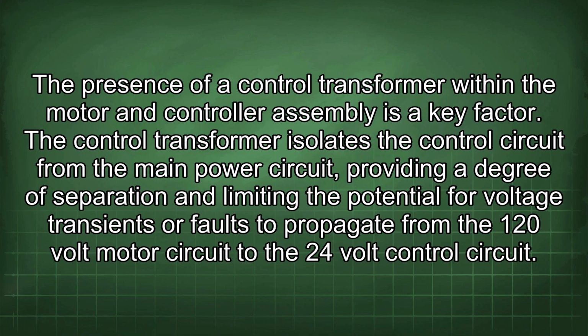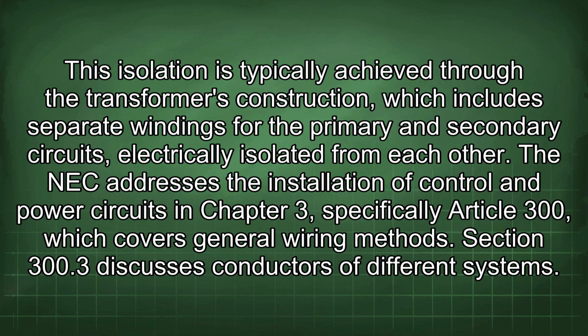The presence of a control transformer within the motor and controller assembly is a key factor. The control transformer isolates the control circuit from the main power circuit, providing a degree of separation and limiting the potential for voltage transients or faults to propagate from the 120-volt motor circuit to the 24-volt control circuit. This isolation is typically achieved through the transformer's construction, which includes separate windings for the primary and secondary circuits, electrically isolated from each other. The NEC addresses the installation of control and power circuits in Chapter 3, specifically Article 300, which covers general wiring methods.